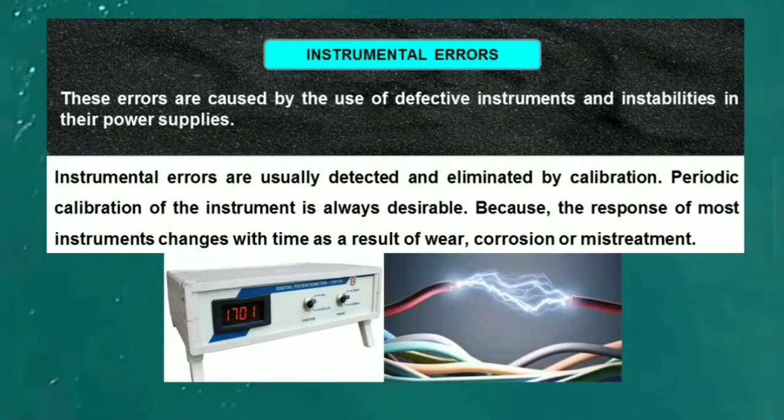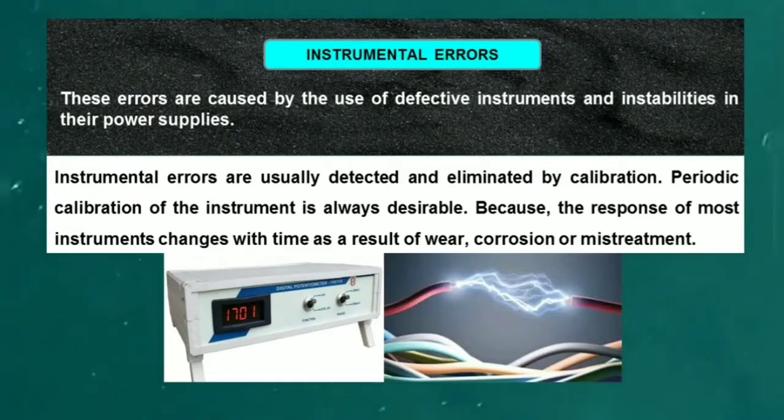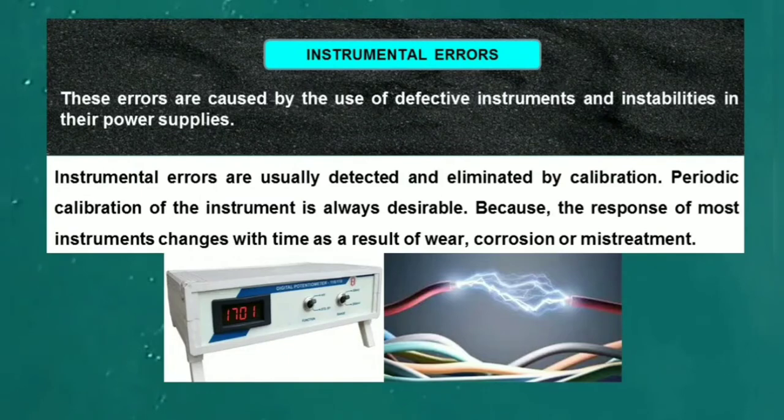Instrumental errors: These errors are caused by the use of defective instruments and instabilities in their power supplies. These errors are usually detected and eliminated by calibration. Periodic calibration of the instrument is always desirable because the response of most instruments like potentiometer and conductometer changes with time as a result of wear, corrosion, or mistreatment.